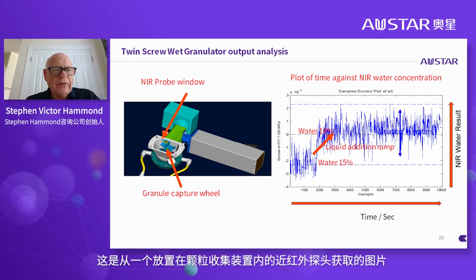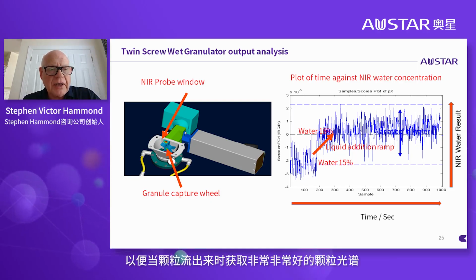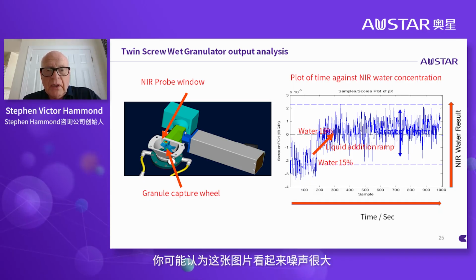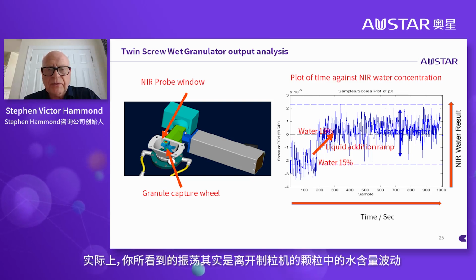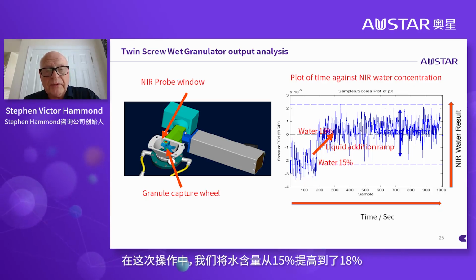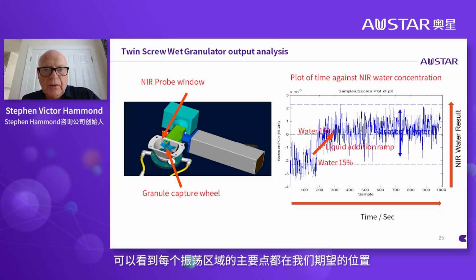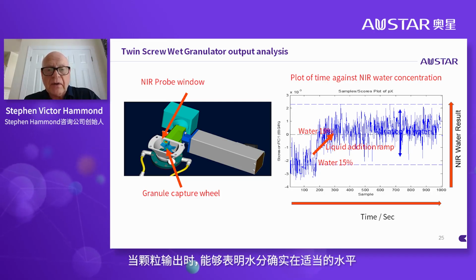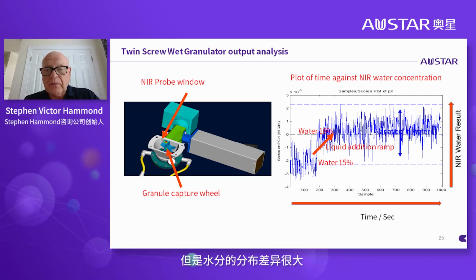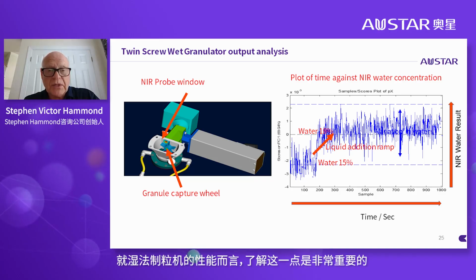So here's the output that we gained from a near-infrared probe that was placed into a device where the granules are captured in front of the probe window and allow us to get very good spectra of the granules as they're coming out in a stream. Now, the plot here looks very noisy, you would think, but in actual fact, the oscillations you see are really the true variation in the water content of granules exiting the granulator. In this exercise, we ramped up from 15% to 18% moisture, so you can see the mean point of each of those oscillating areas is where we'd expect it to be. As the granules are exiting, they're showing that the water is indeed at the right level, but it is quite variable in terms of its distribution, which is very important to understand in terms of the performance of the wet granulator.